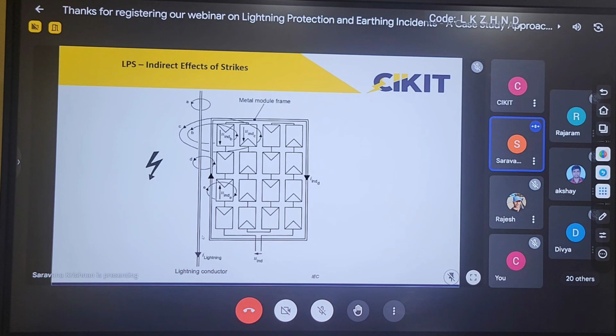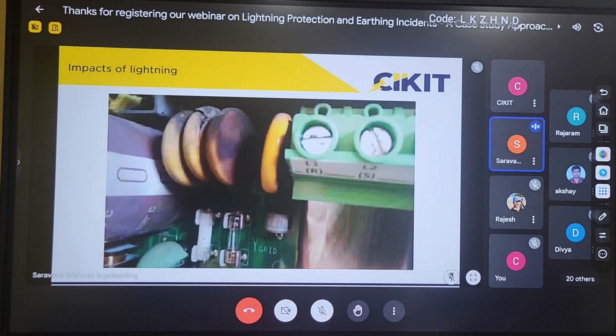So if the surge has some impact, an EMF is induced, which means the electronic equipment connected to that particular power line or data line will get affected. To avoid this, you have to go for surge protection devices. In this image, you can closely observe that the electronic equipment got damaged, and below this electronic component there was a fuse provided. Even though we provided the fuse, the electronic component was not protected. The actual reason is that the damage was caused by the surges.